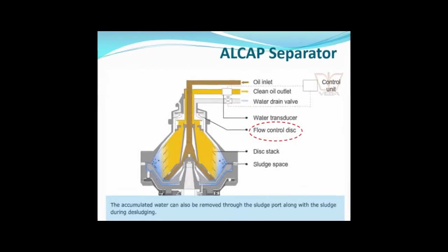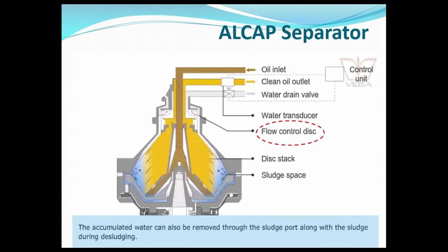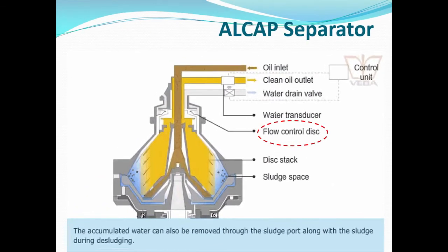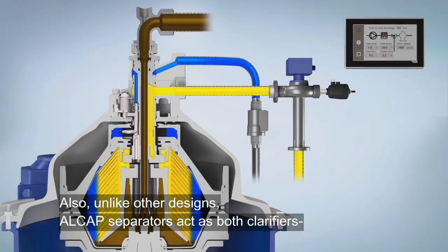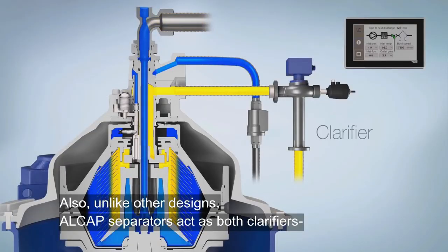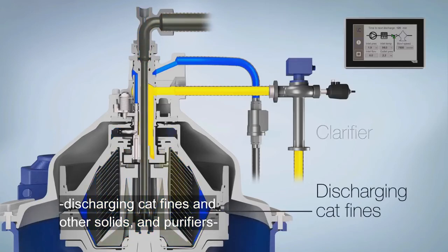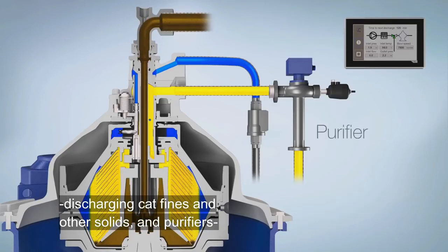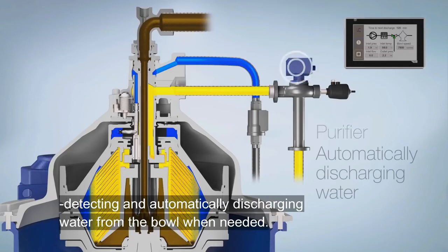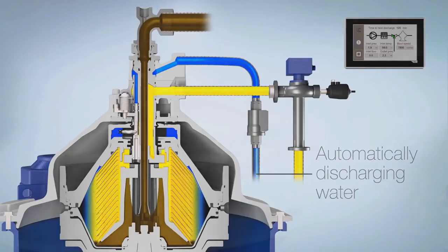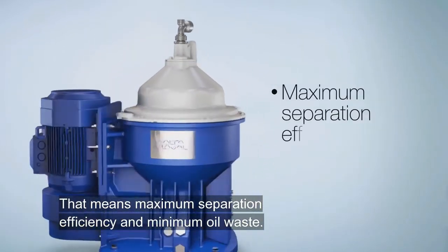The separator uses a flow control disc, instead of the standard gravity disc. Also, unlike other designs, ALCAP separator act as both clarifier, discharging cat fines and other solids, and purifier, detecting and automatically discharging water from the bowl when needed. That means maximum separation efficiency, and minimum oil waste.